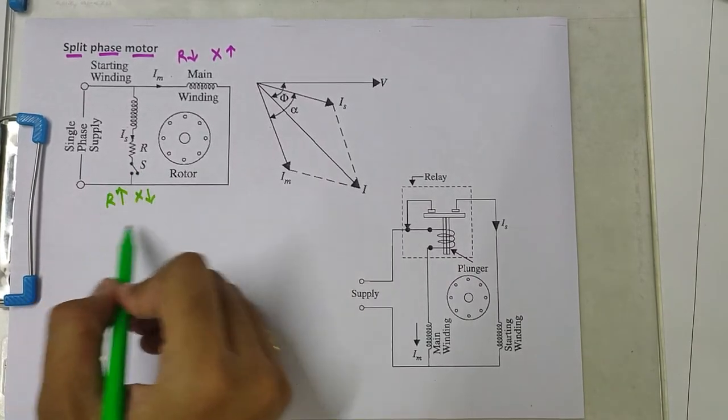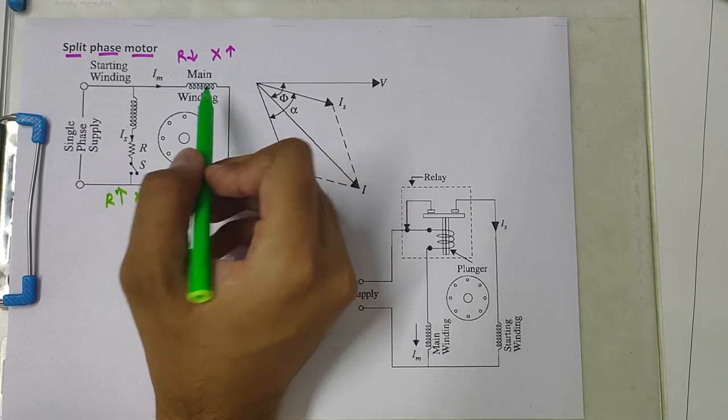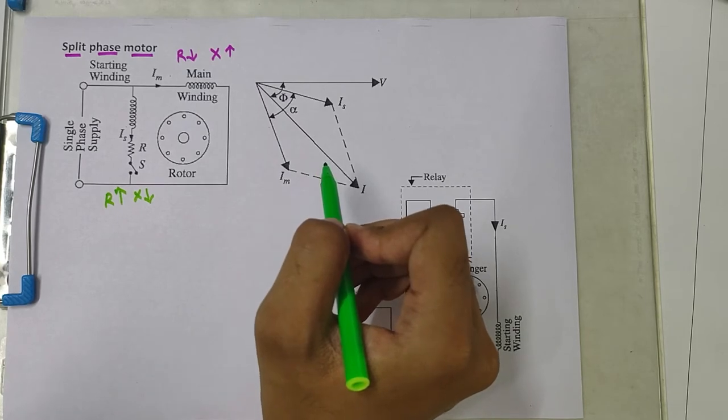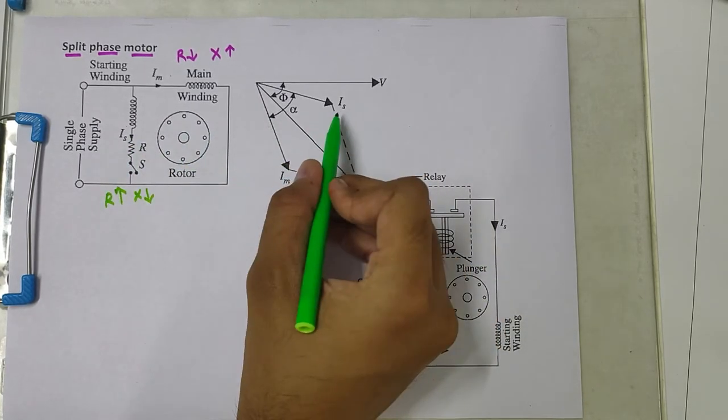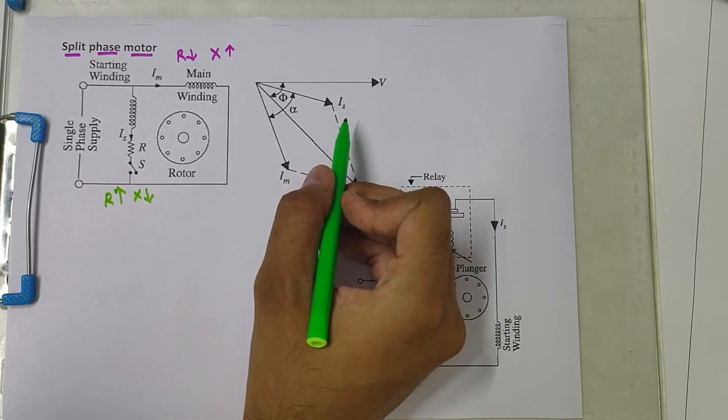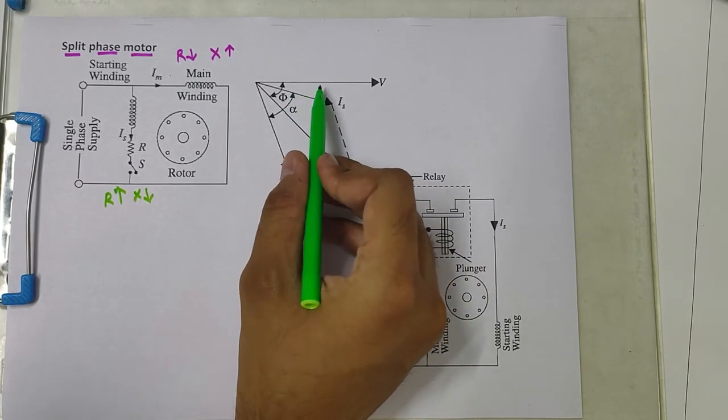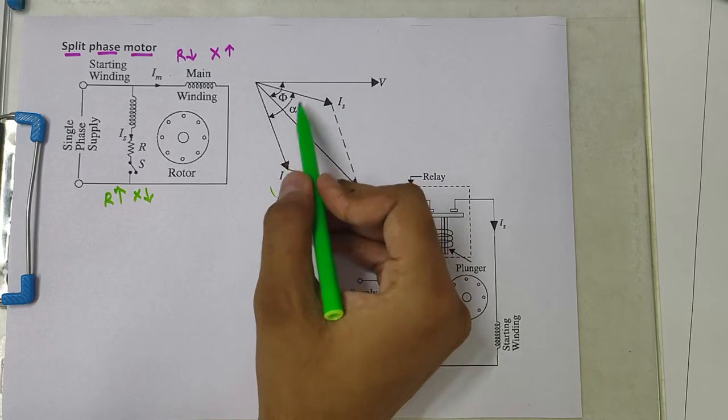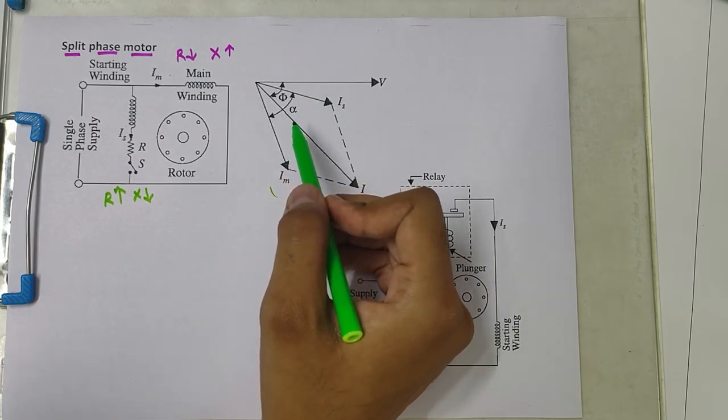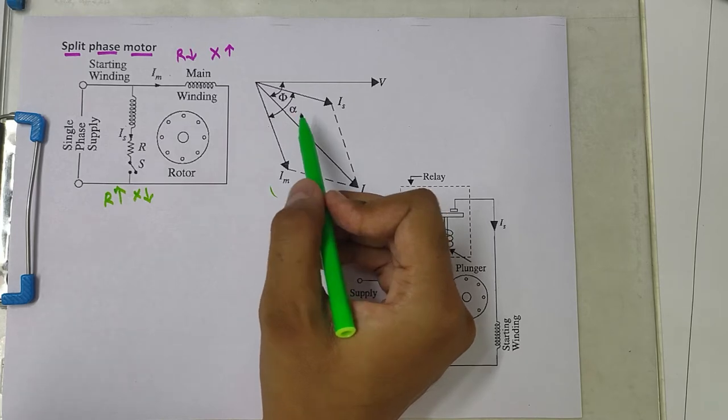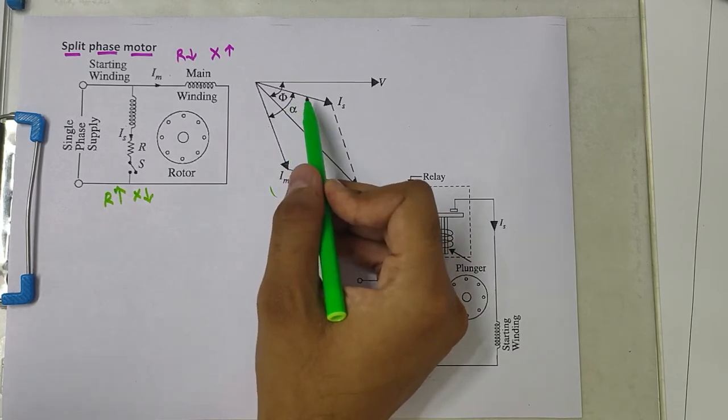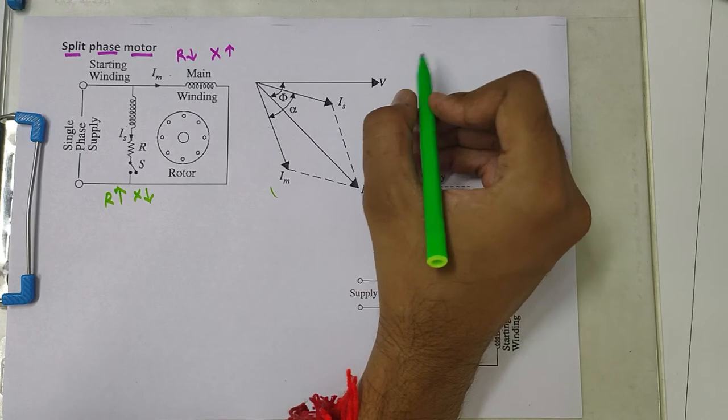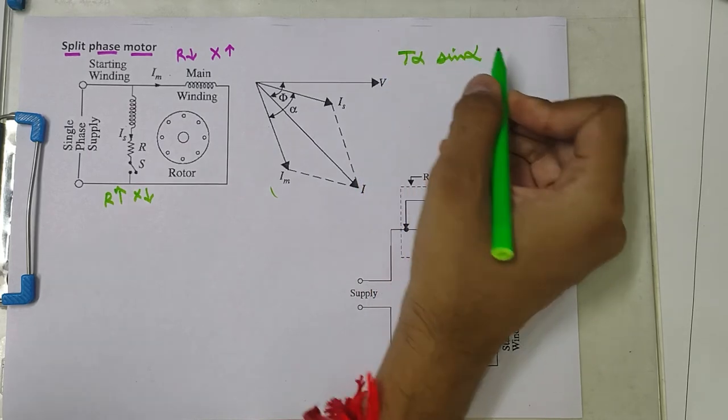So because of this change in resistance and reactance of the main winding and starting winding, as you can see in the phasor diagram, the current drawn by the starting winding which is indicated by IS lags behind the applied voltage by a small angle, whereas the current of the main winding indicated by IM lags with the applied voltage by a large angle. The phase angle between IS and IM is made as large as possible. The alpha must be as large as possible because the torque of a split phase induction motor is directly proportional to sin alpha.